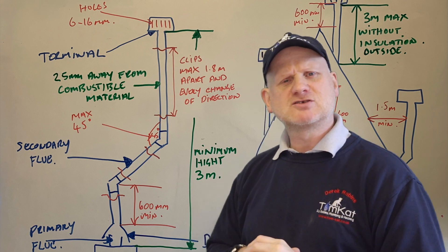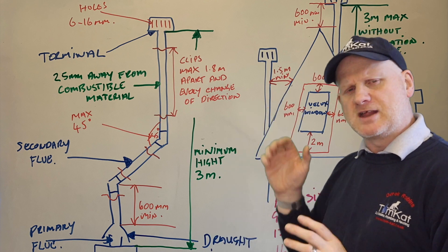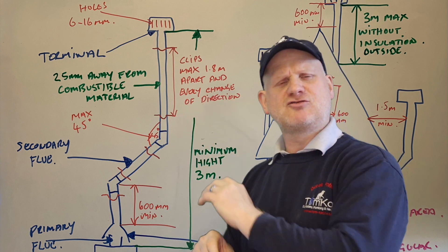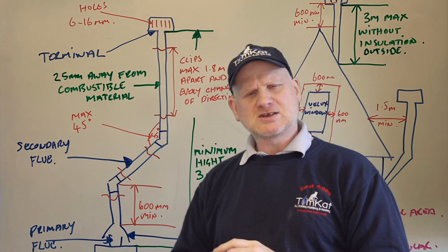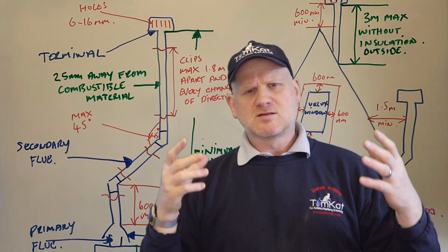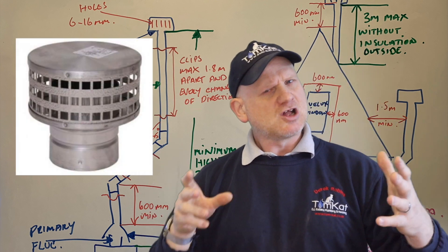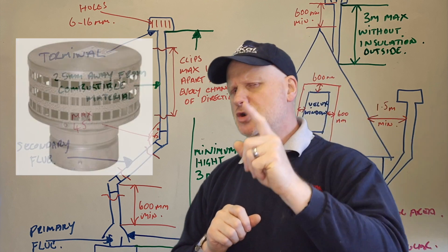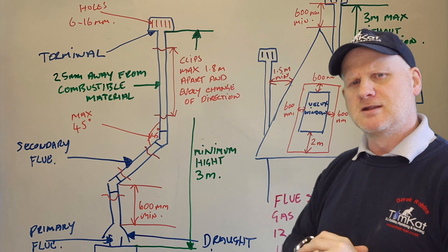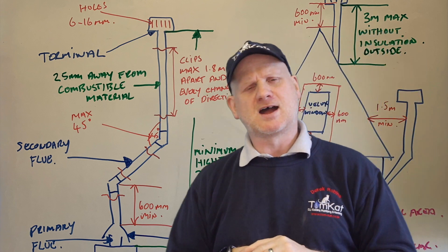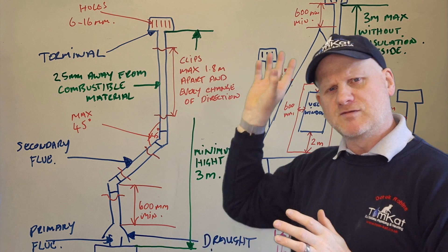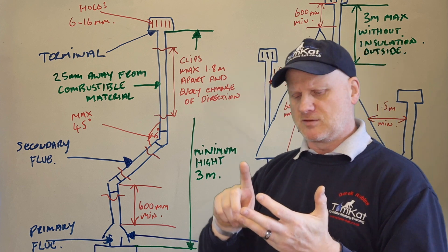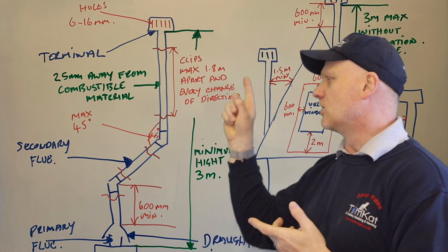The maximum height is per manufacturer's instructions — check those. At the top of the secondary flue is the terminal. The slots or holes in the terminal must allow the passing of a 6mm ball but not a 16mm ball. So those are the major components: primary flue, draft diverter, secondary flue, and terminal.